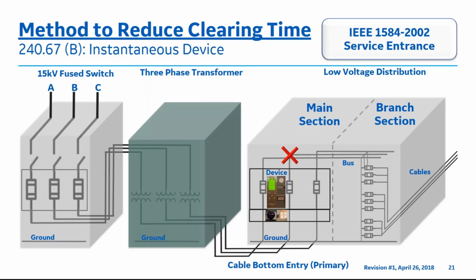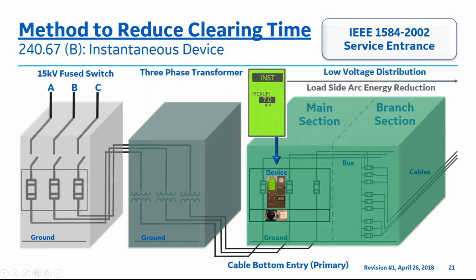These statistics are extremely relevant, as the NFPA data correlates to the application examples presented in this webinar and specifically in this slide. For 240.67B, the instantaneous device, during an arcing fault with the red X shown here, the electronic device would measure and clear the arcing fault event shown here and provide load side arc energy reduction for this section of the low voltage distribution equipment. This device protects and affects the arc flash incident energy label of everything inside this zone, including the entire main section and branch section, such as a switchboard application.